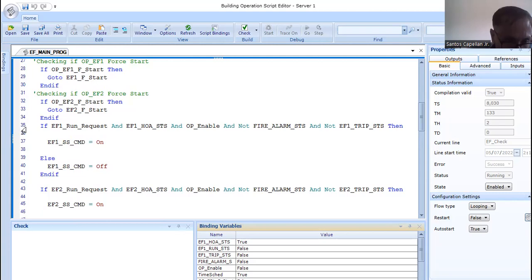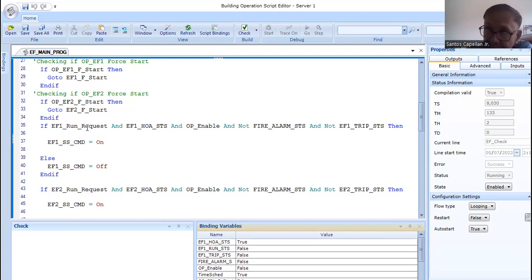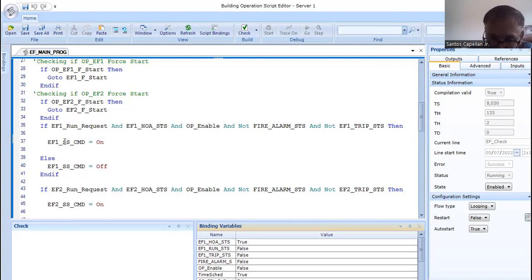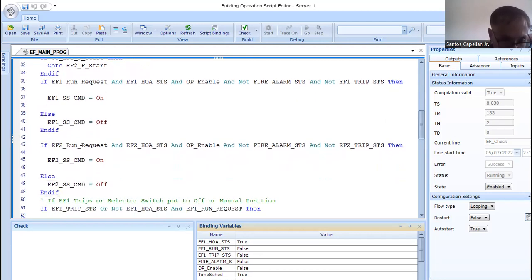At line 35, the program checks for a run request, which is manipulated in the EF run accumulation program. If the run request is true, hand/auto status is true, operator enable is true, fire alarm is false, and EF1 trip is false, then EF1 starts. Otherwise, in the else condition, it checks EF2 run request with the same logic — if true, EF2 starts.